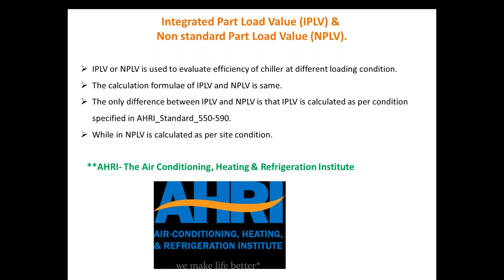Clear? And if you are not following this standard 550-590 and you are evaluating the part load value or the performance of your chiller based on the site conditions or your local conditions, then it is called a non-standard part load value. So for IPLV and NPLV the formula remains the same; the only difference is the conditions based on which you are doing the trial or testing your device.